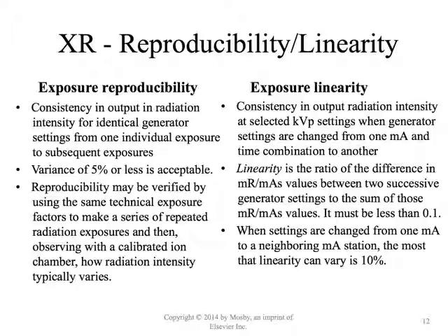Okay, winding down with the X-ray stuff, we'll talk about reproducibility and linearity. I've put these side by side. I know this is kind of a busy slide, but this is something that students struggle with quite a bit, the difference between reproducibility and linearity. If you can imagine, reproducibility is just taking the same exposure over and over again. Each one of those exposures should be within 5% of the previous exposure. So any exposure made at like 2.5 mAs should be pretty much within 5% of each other exposure at 2.5 mAs. That's reproducibility.